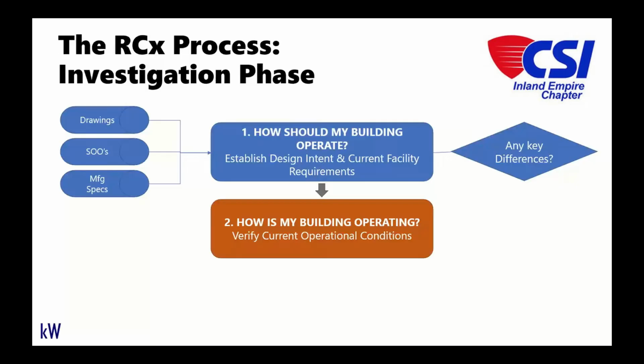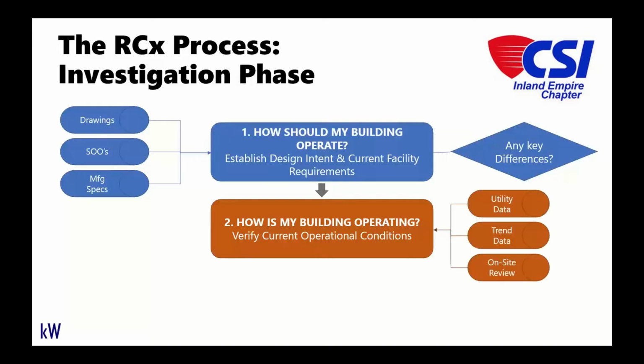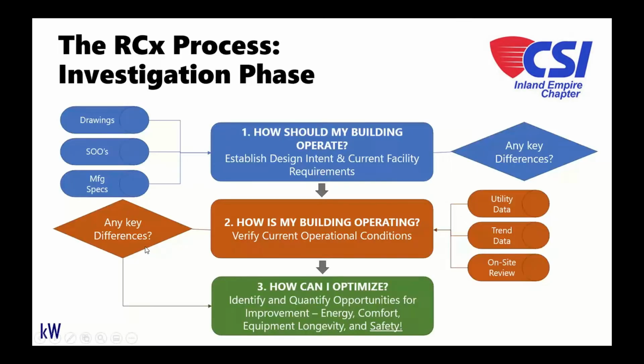Additionally, we also like to ask, how is the building, or campus of buildings, currently operating? So we want to verify the current operational conditions. That process will often use utility data, trend data from your building management system, and physical on-site review of systems to determine if your current system operations are actually in line with your facility requirements and the design intent. And again, we want to ask ourselves, are there any key differences between what's currently happening versus how the buildings were designed? And really, those key differences are what drive optimization.